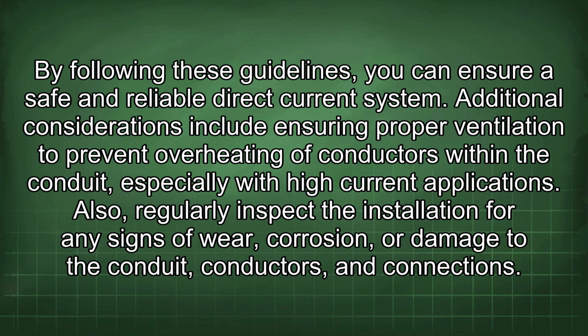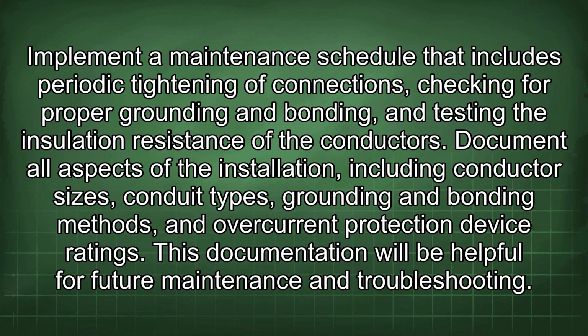Additional considerations include ensuring proper ventilation to prevent overheating of conductors within the conduit, especially with high current applications. Also, regularly inspect the installation for any signs of wear, corrosion, or damage to the conduit, conductors, and connections. Implement a maintenance schedule that includes periodic tightening of connections, checking for proper grounding and bonding, and testing the insulation resistance of the conductors. Document all aspects of the installation, including conductor sizes, conduit types, grounding and bonding methods, and overcurrent protection device ratings. This documentation will be helpful for future maintenance and troubleshooting.